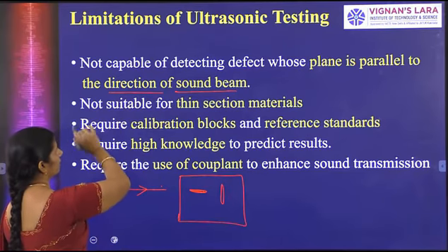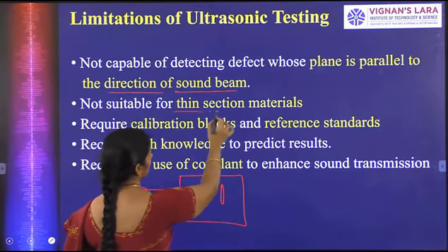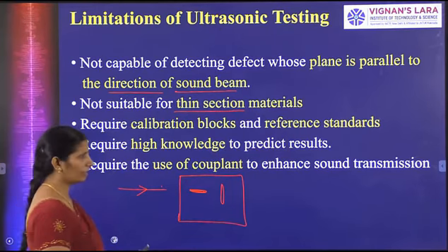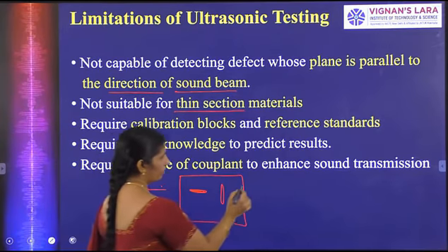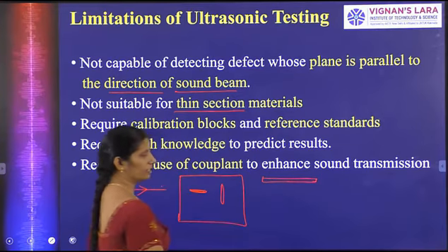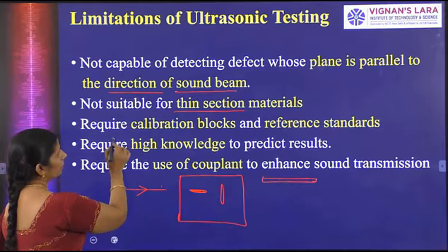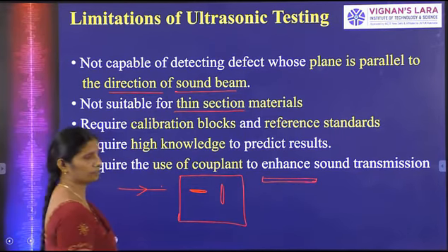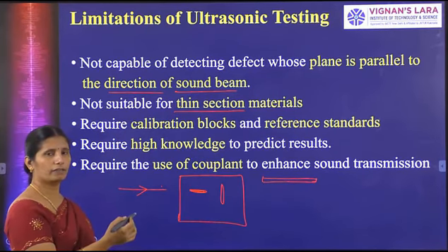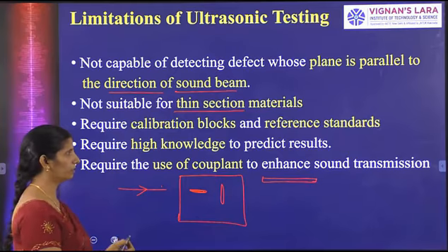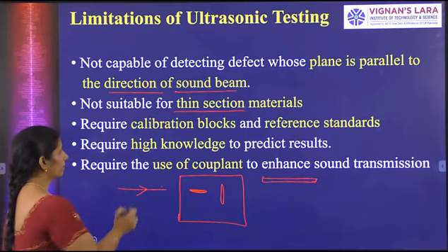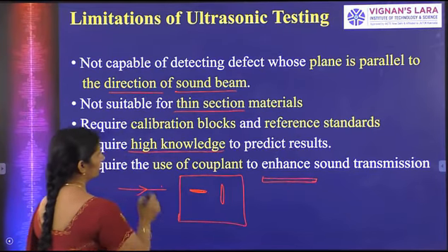That is one of the disadvantages. They are also not suitable for thin section material. This testing is applicable only for thick materials, and it is not suitable for thin materials, which are very lean. They require calibration blocks and reference standards. For using ultrasonic testing, we should have some reference levels, reference standards and calibration blocks. That is one of the limitations.